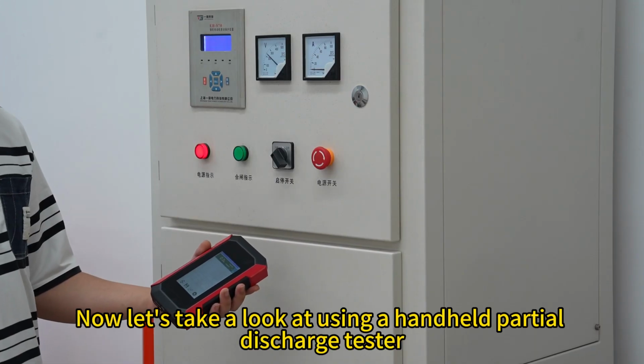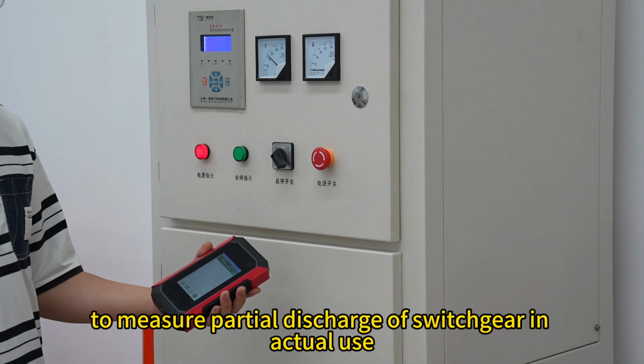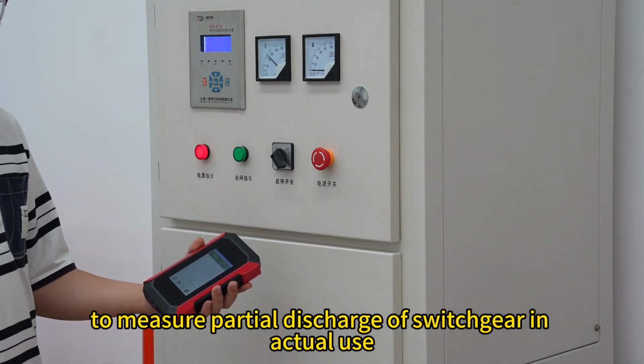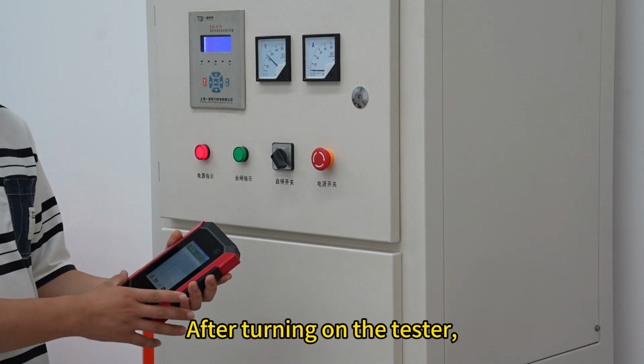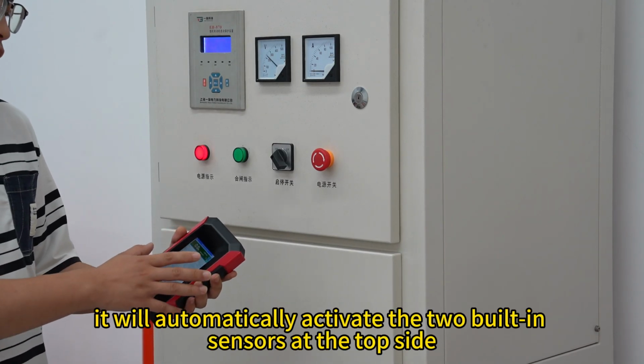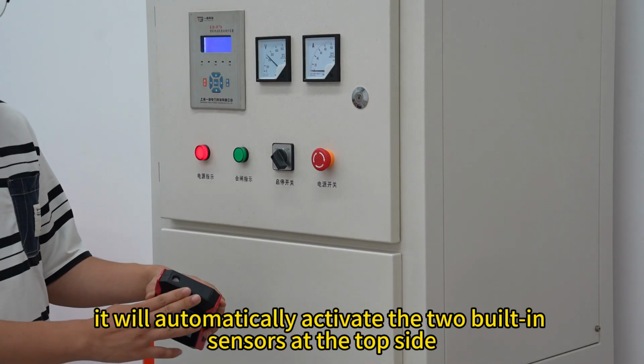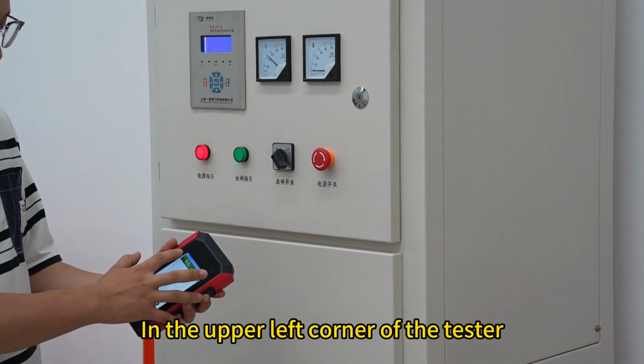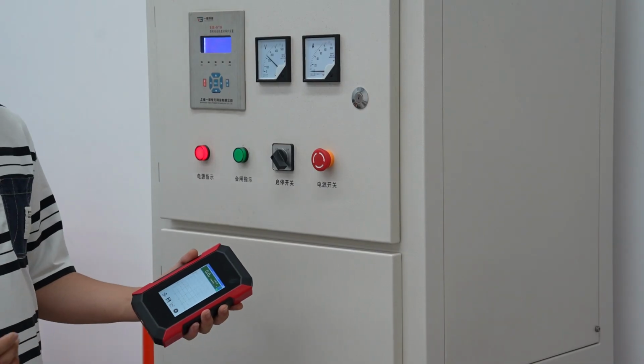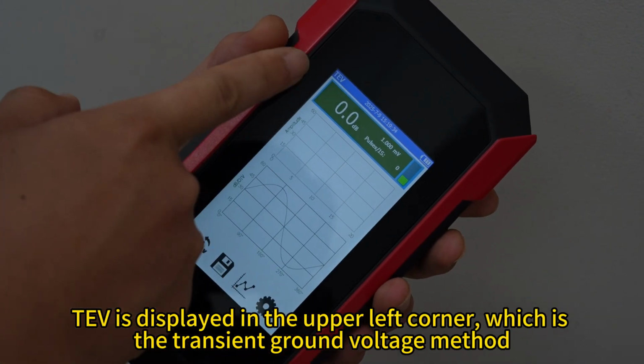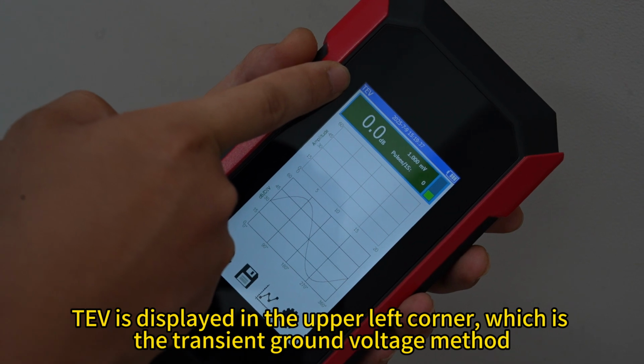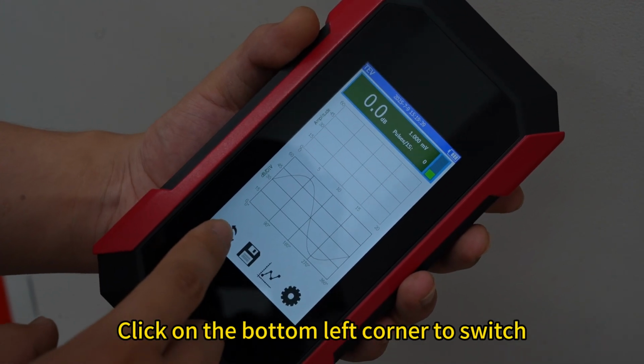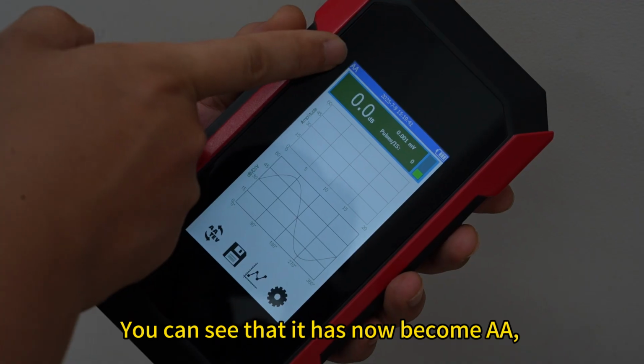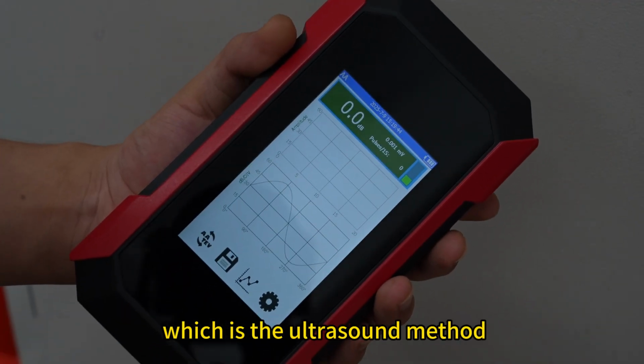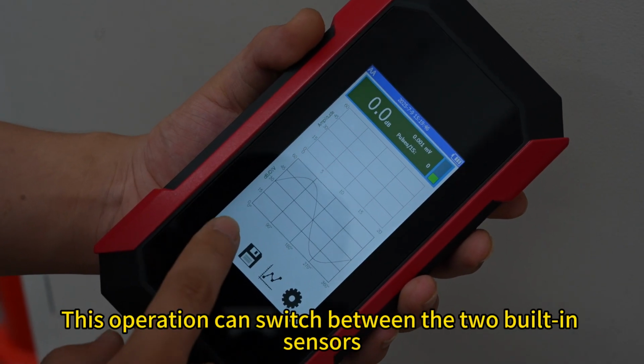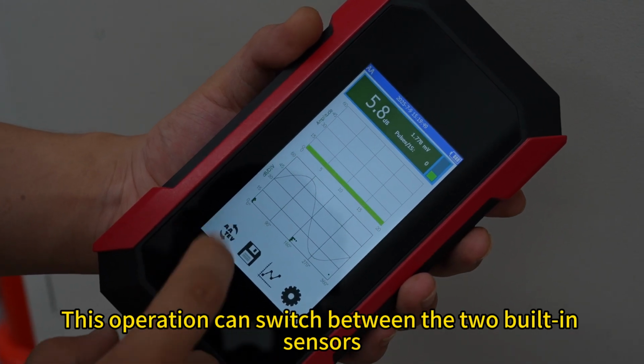Now let's take a look at using the handheld partial discharge tester to measure partial discharge of switchgear in actual use. After turning on the tester, it will automatically activate the two built-in sensors at the top side. After turning on the tester, TEV is displayed in the upper left corner, which is the transient earth voltage method. Click on the bottom left corner to switch. You can see that it has now become AA, which is the ultrasound method. This operation can switch between the two built-in sensors.